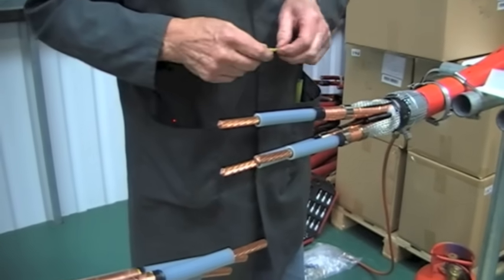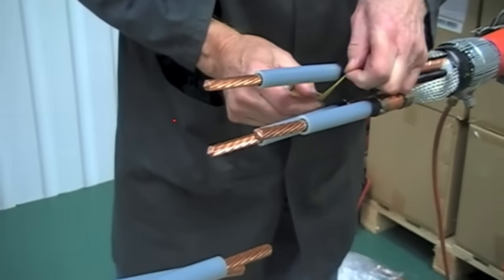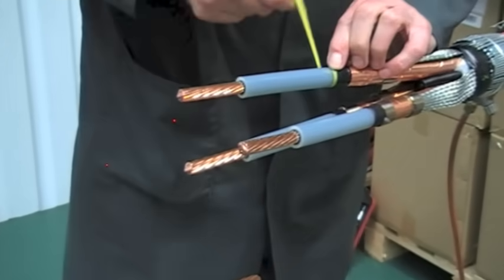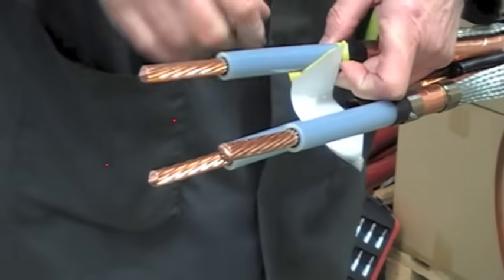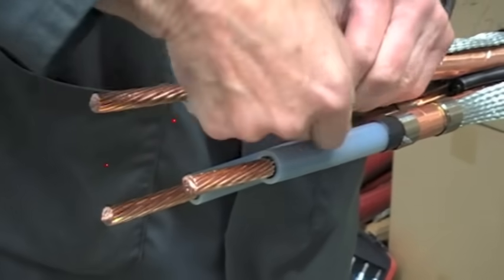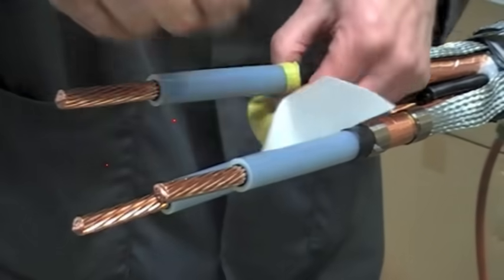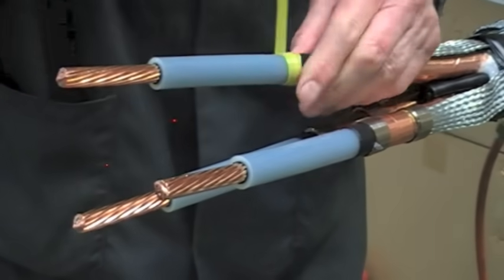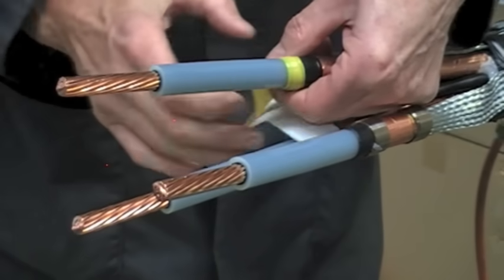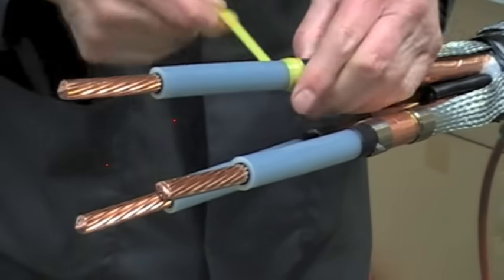Now take the yellow stress relieving mastic, apply with a thin edge, stretch and extend onto the primary insulation by 10mm, back onto the semi-conductive layer and just catch the copper tape screens to keep them in position.